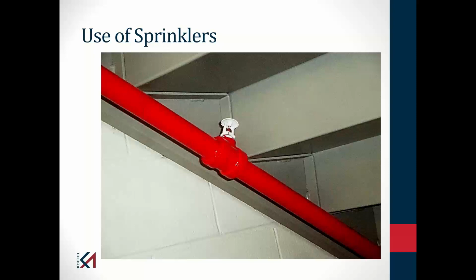It will tell me whether it's standard response or fast response. It will tell me whether it's an upright sprinkler like we see here, or a pendant sprinkler that should be below the pipe, or a sidewall sprinkler. So it'll tell me the orientation of the sprinkler. And there are other characteristics that it will tell me as well. But again, those are all important performance characteristics.